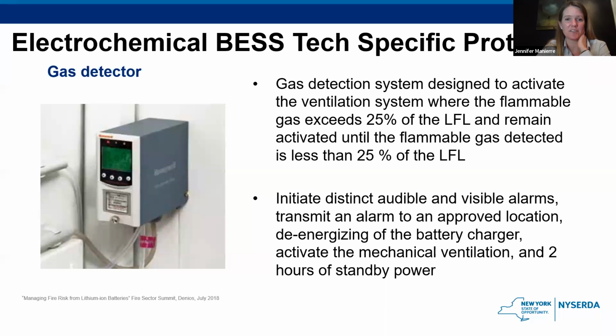Obviously, you need a gas detector to know when to activate the ventilation system, especially if you're using that 25% of the lower flammability limit threshold. And it needs to make sure that the ventilation remains activated until the gas gets below that 25% lower flammability level, and be able to set off audible and visible alarms and transmit an alarm again to that approved location, probably somewhere offsite, that central station that's monitoring everything, and also be capable of de-energizing the battery charger, activating the ventilation, and again, have 2 hours of standby power, just like the ventilation itself.